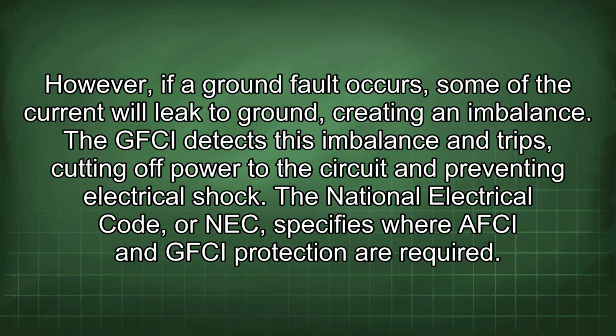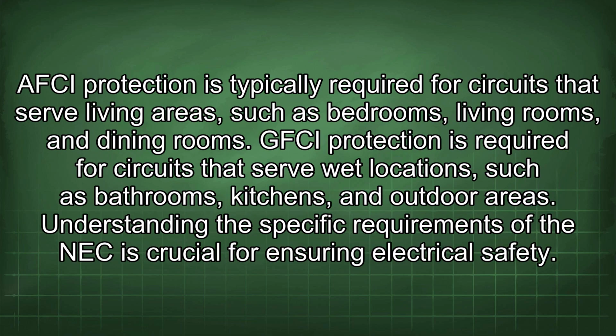The National Electrical Code, or NEC, specifies where AFCI and GFCI protection are required. AFCI protection is typically required for circuits that serve living areas, such as bedrooms, living rooms, and dining rooms. GFCI protection is required for circuits that serve wet locations, such as bathrooms, kitchens, and outdoor areas. Understanding the specific requirements of the NEC is crucial for ensuring electrical safety.